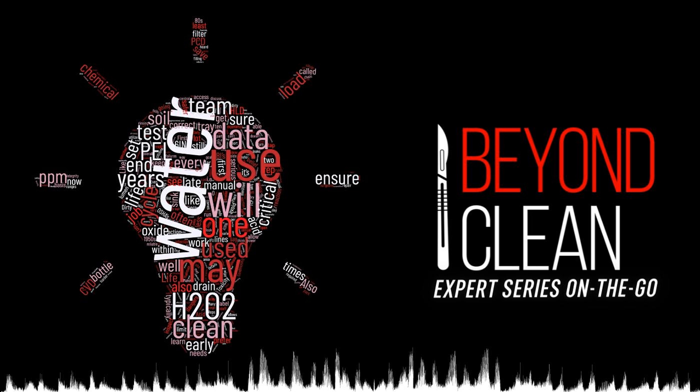Repair only. This type of program may be called different names depending on the vendor, but simply stated, it is the most basic type of program. The approach is simple. The repair vendor will only service those instruments that have been identified as not functioning correctly or as in need of sharpening. This type of program could be employed via an on-site mobile van on a scheduled basis or as needed. Typically, this type of program is going to be the most cost-efficient program for your facility.